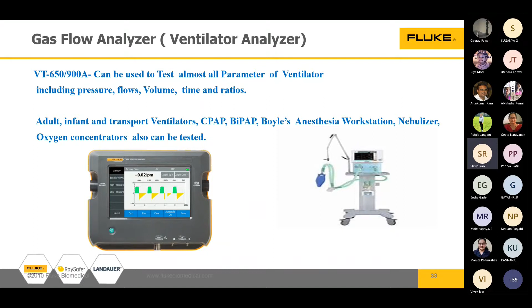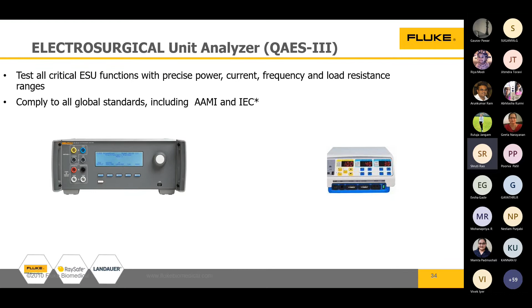Similar thing with electrosurgical unit analyzers. So you test all those cautery machines in the hospital. What you have to cross-check is whether the power distribution is correct. If I am saying it is 400 watts, whether 400 watts is there or not. Current, frequency, load resistance ranges as per IEC standard. We are not talking about anything which is not as per the standards. We are following the global standards.